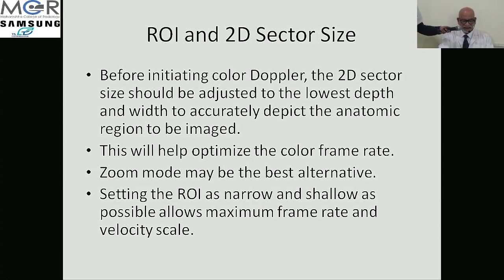Setting the ROI, the region of interest, as narrow and shallow as possible allows a maximum frame rate and velocity scale. If you want to study the mitral valve, then the sector width and depth should be such that they cover the mitral valve only. If you want to study the flow from the mitral valve up to the roof of the left atrium, then you have to increase the depth. So, keeping the sector size to a minimum, you can get the best possible result.